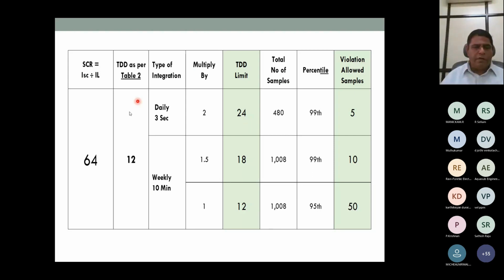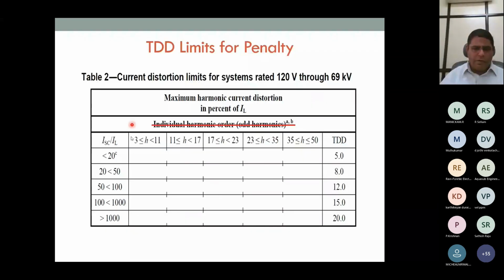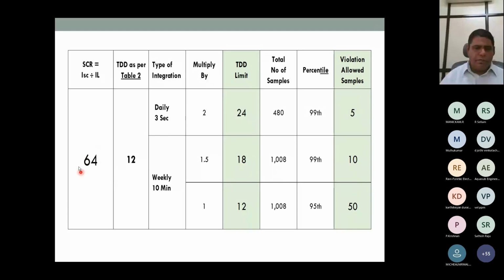Say, for example, the short circuit ratio is 64. So TDD as per the earlier table, 64 comes here. So the limit is 12%. So I have written 12 here, 64 here. There will be three types of readings. Daily, there will be one reading, as we have seen in voltage harmonics. But weekly, there will be 2 percentiles. That is, 10 minute values, 2 percentiles will be evaluated. So for daily, they are giving a multiplication factor of 2. So 12 becomes 24. So till 24% we can go, and the total number of samples will be 480, and 5 samples will be allowed to exceed this 24%.